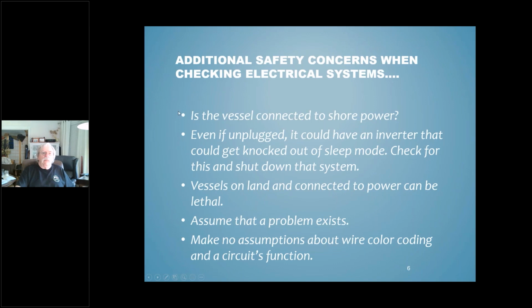So, other items: is the vessel connected to shore power? And even if unplugged, again, the inverter is a real possibility. It's happened to me, I know. And the other one that many of you probably experience, a vessel on land, up on the hard, and you go over to the boat and you touch the prop shaft and you get zapped. It is plugged in. Don't rely on the grounding system at a receptacle out in the back 40 of the marina. Odds are really good that the ground is not good. Assume that a problem exists.